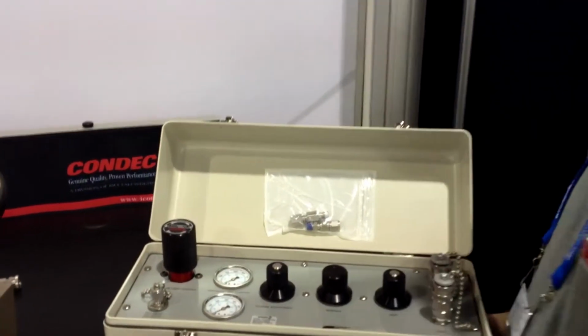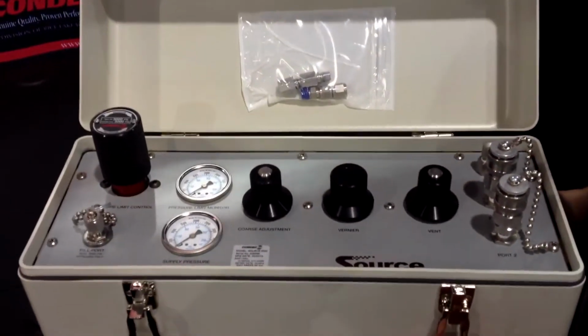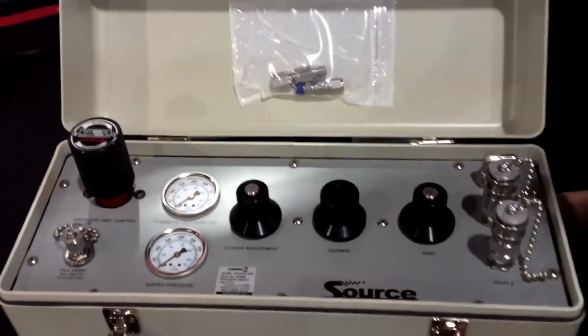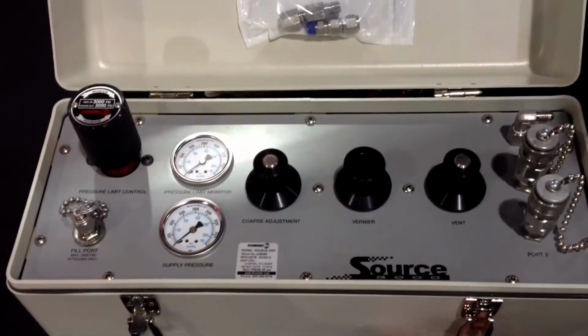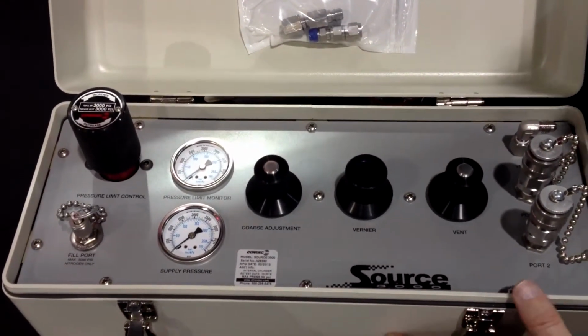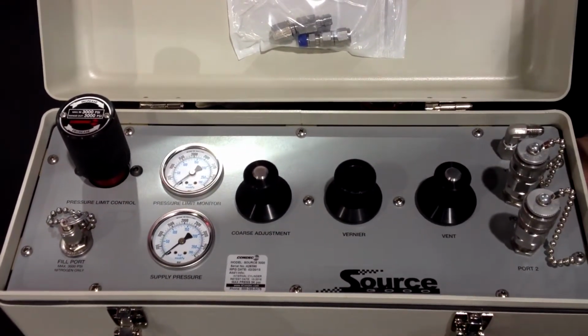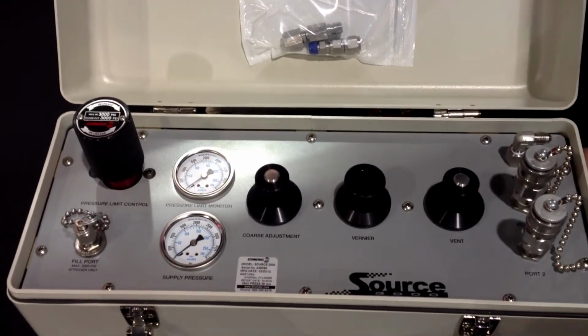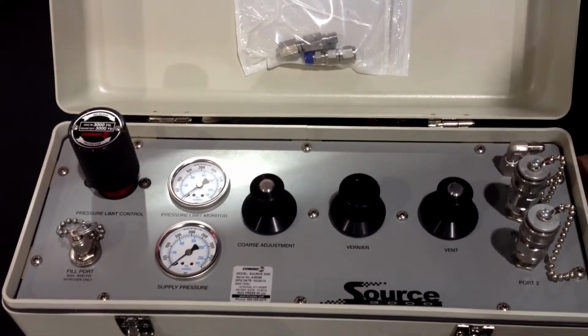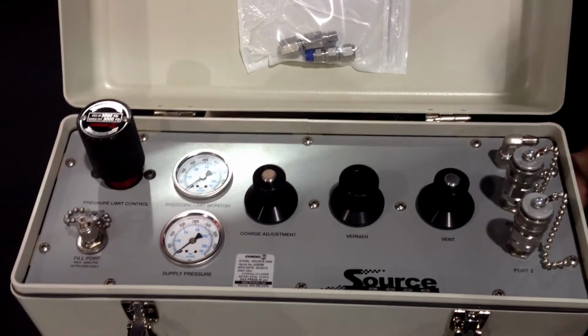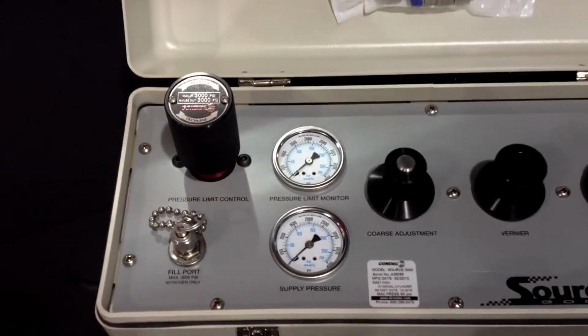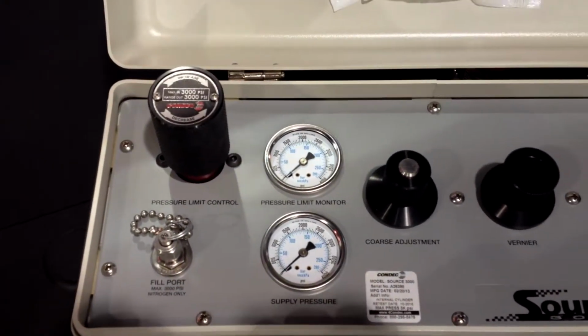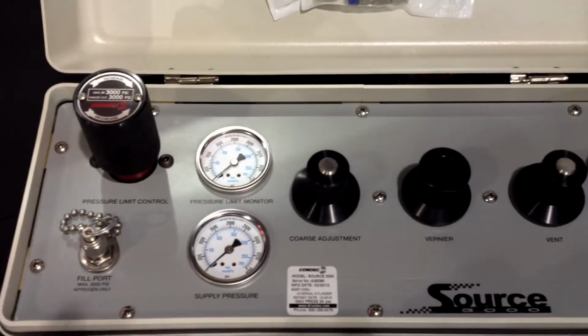How it operates is we have an internal nitrogen cylinder. You would fill it back up at your shop or at your facility. You're then able to take it on site to do your calibrations, whether it be for pressure switches, analog gauges, digital gauges, transducers, transmitters, anything that you need to verify or calibrate that has to do with pressure.